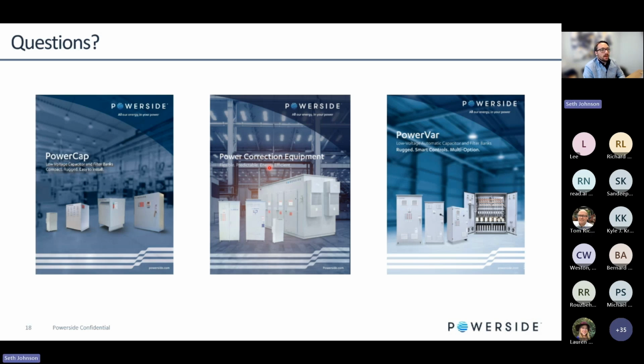Super. Yeah. So, Eric, great question. The fact of the matter is that there is no such thing as a guaranteed grid impedance by the utility, at least not nowadays, especially with all the inverter-based resources and cogeneration, and we're moving away from centralized power generation, which is impacting really the modern power distribution system. So in most cases, you're looking at worst case scenarios. So we'll work with utilities to give us typical scenarios as well as worst case scenarios, and then we'll adjust according to that.